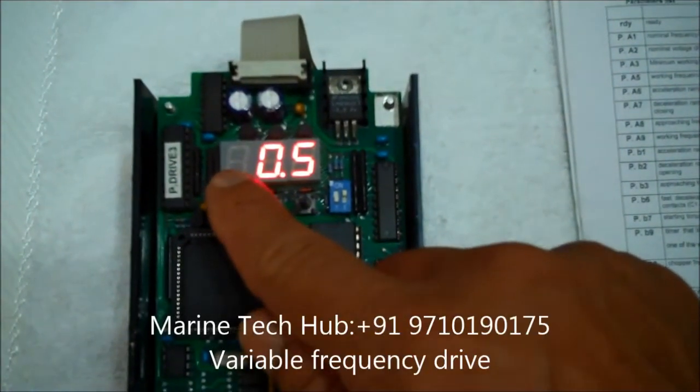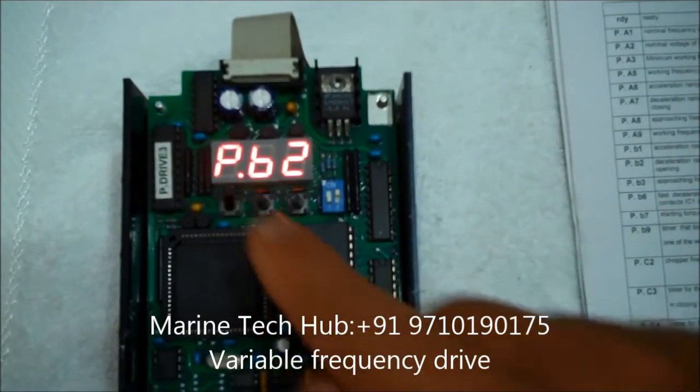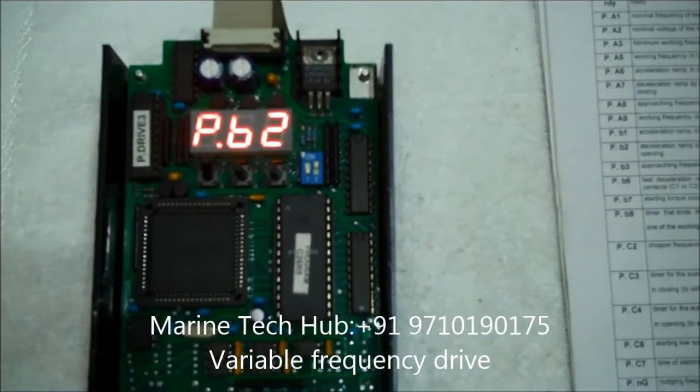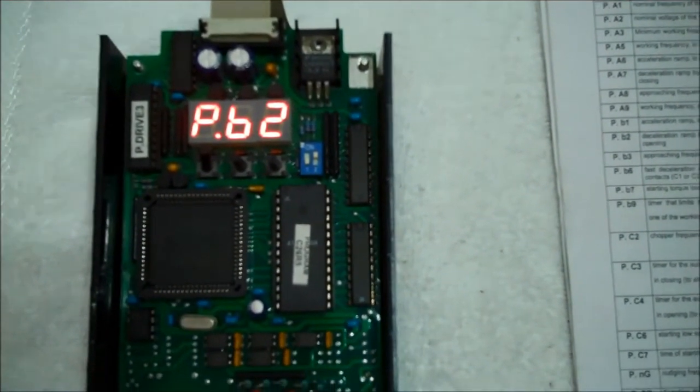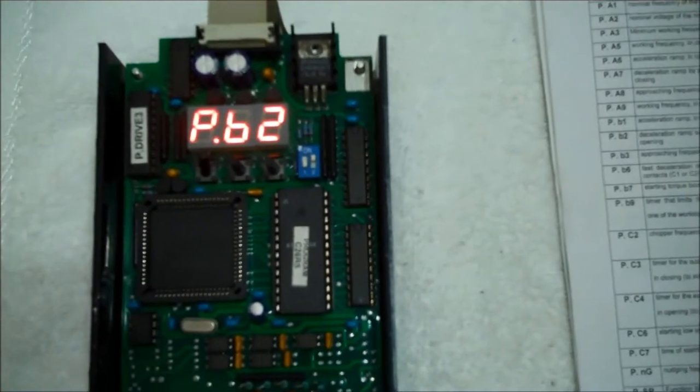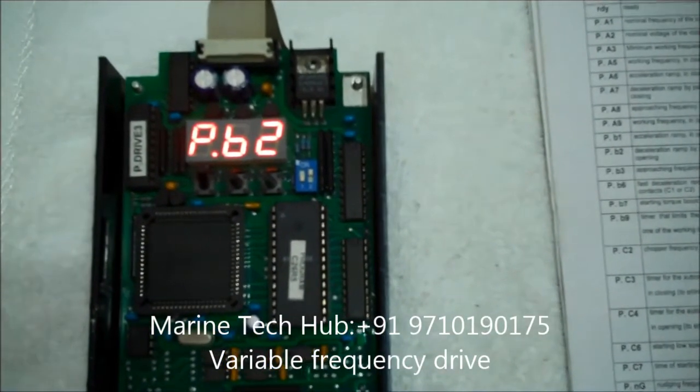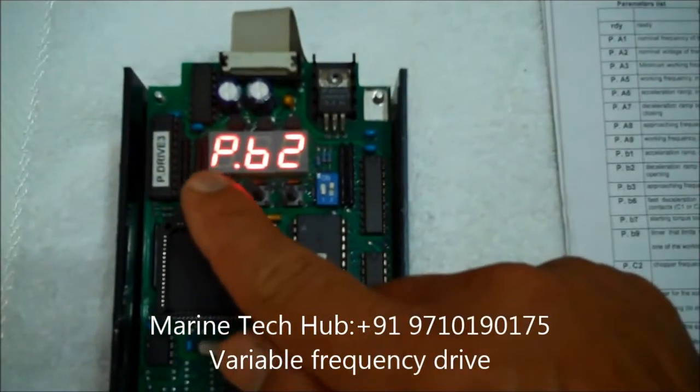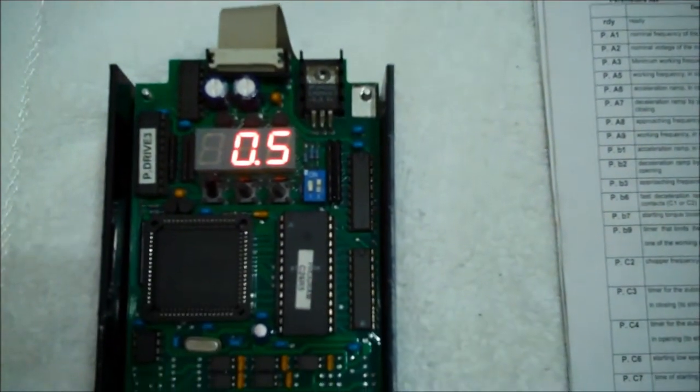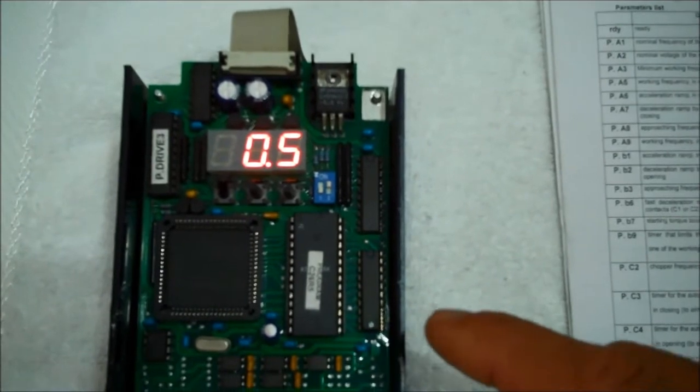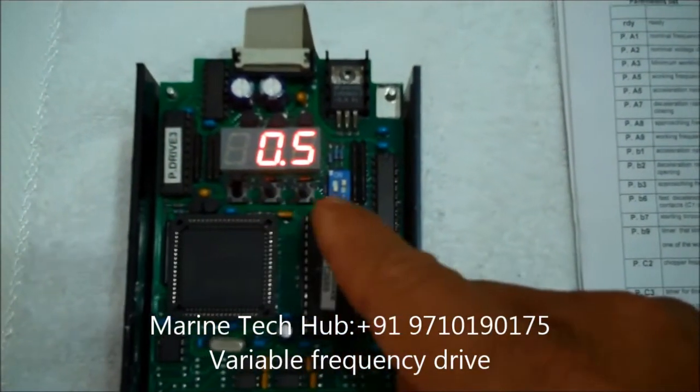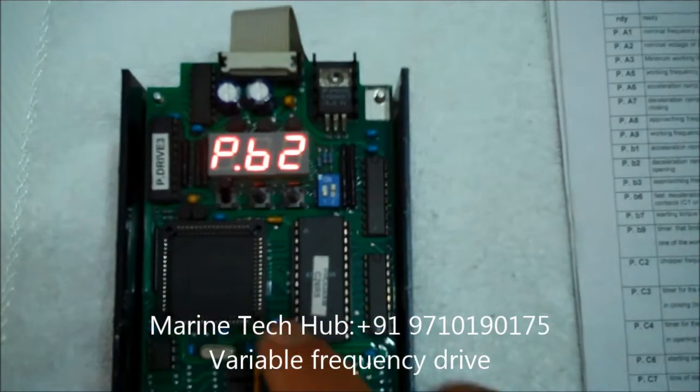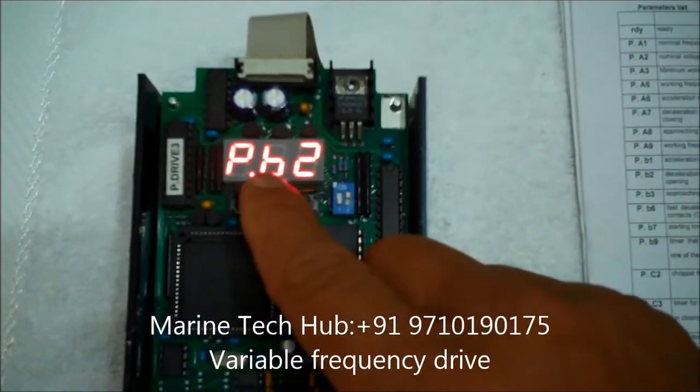So next program is PB2. PB2 is deceleration ramp passing from high to low speed in opening. This is also in seconds. This is programmed to 0.5 seconds. So this program has been done. You can change the seconds also. I don't want to do that.